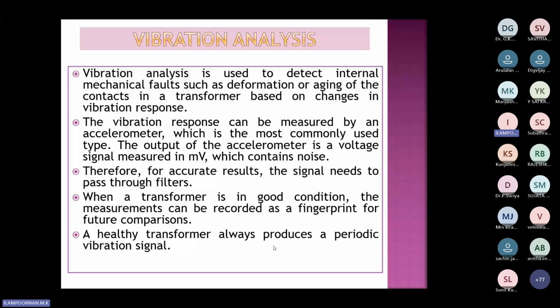The last one is vibration analysis. You can take this as a signature, since vibration is a physical phenomenon. When you increase the frequency of the signal, for example from 50 hertz to double at 100 hertz, your core will vibrate and produce a vibrating frequency that can be stored as a signature. So if you do the same 100 hertz test on a 40 year old transformer, it will give a different vibration, and based on that you can understand what is happening with the transformer.